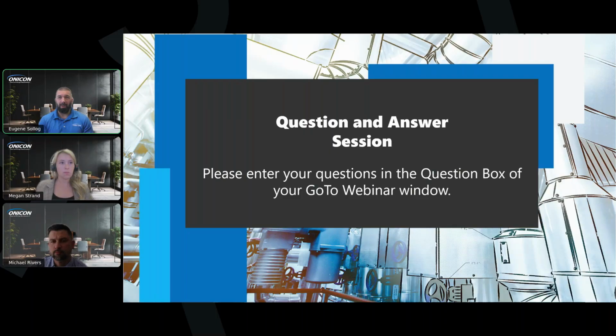If you do need to do something as far as recalibration, we recommend doing a verification. Get out there, call your rep, throw a clamp-on meter out there, or a different meter, and check that, just like we did in that example at the end of the presentation with the FP4400. Thanks, Gino. We even see some engineers put a ball valve downstream of an inline mag meter with new construction. It gives you the opportunity to help validate those flow meters years down the road.